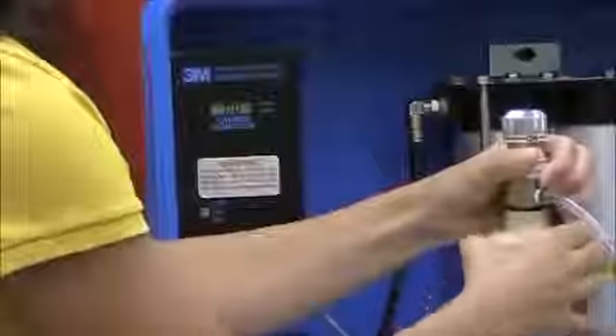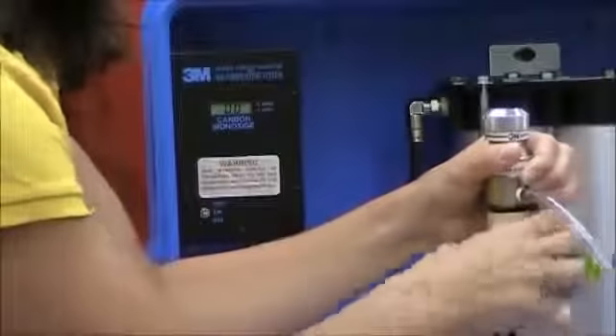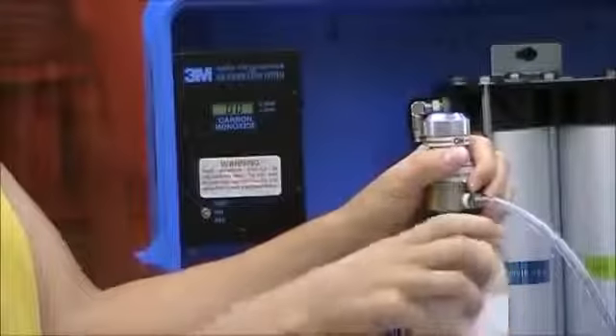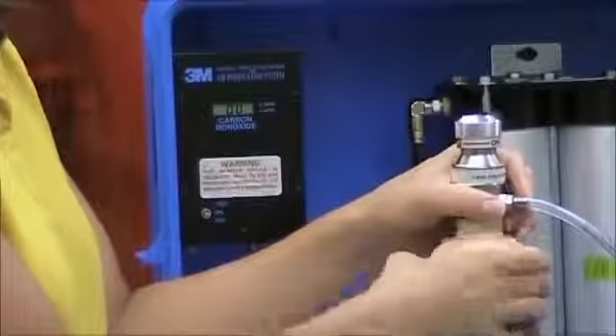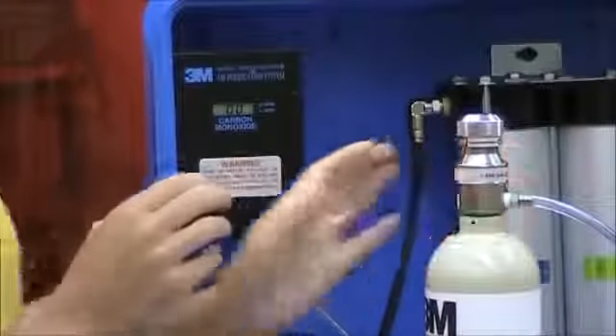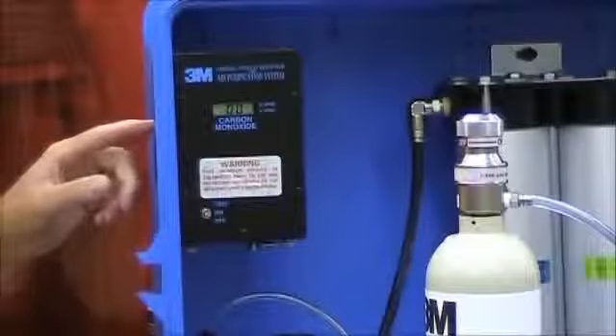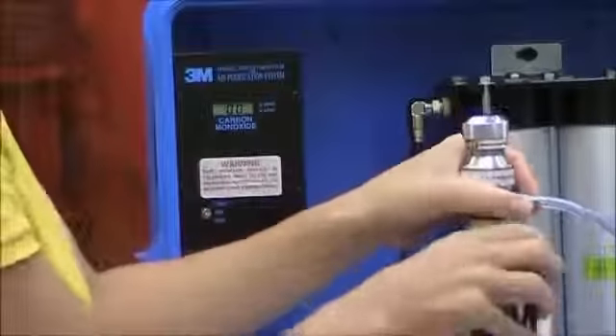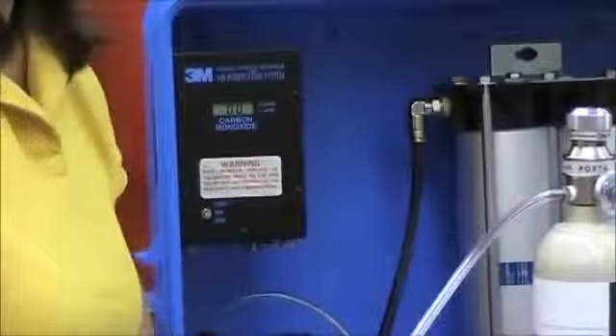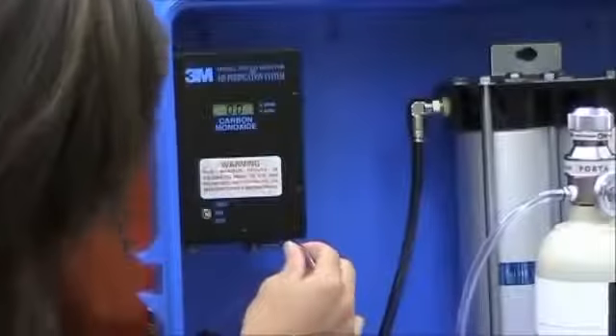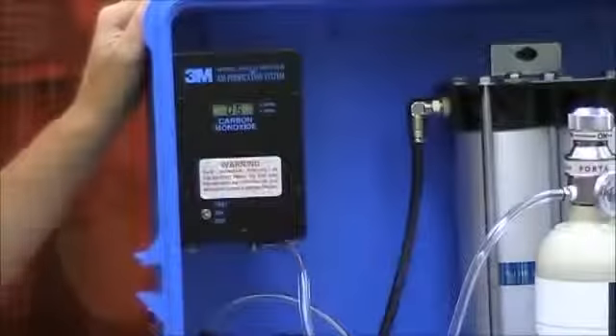I'm going to switch my regulator over to my bottle that has the 95 parts per million carbon monoxide. Now my alarm is set to go off at 10 parts per million, so when I start the flow of gas, I want to make sure that my alarm actually does go off at 10 parts per million. So I'll be able to hear the audible alarm, and then on the right side of the panel over here, I'll see my visual alarm, which is a red light, turn on at 10 parts per million. It should go up to approximately 95 parts per million, and if I need to adjust it, I will do the same by adjusting the span potentiometer.